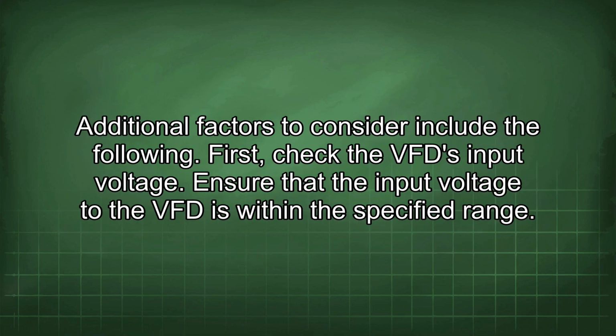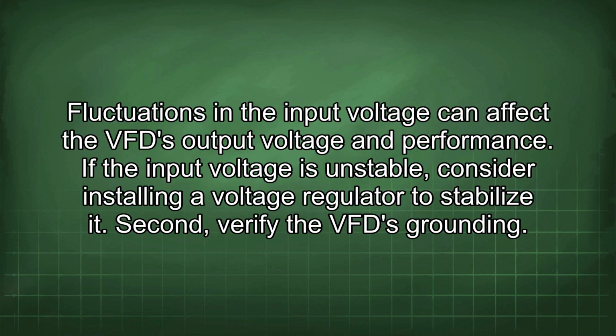Additional factors to consider include the following. First, check the VFD input voltage. Ensure that the input voltage to the VFD is within the specified range. Fluctuations in the input voltage can affect the VFD output voltage and performance. If the input voltage is unstable, consider installing a voltage regulator to stabilize it.